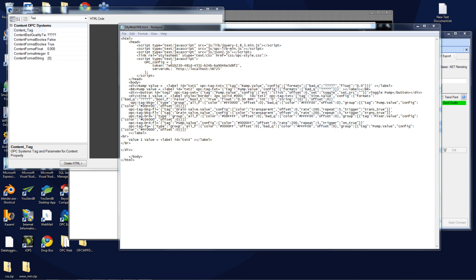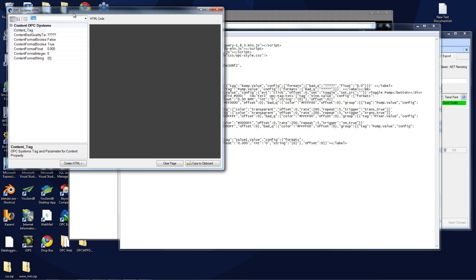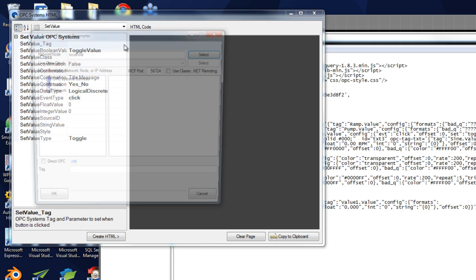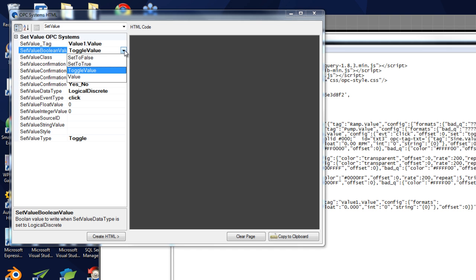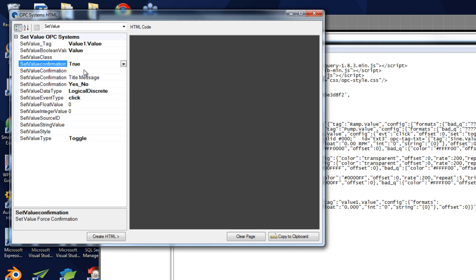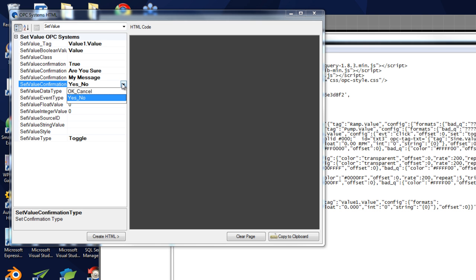One other important property to look at is the set value. This allows you to use any element in your HTML application to set a value in an OPC Systems tag. Currently you need to be monitoring that value for the set value to work. I've created a label called value1, given it an ID, and now we're going to monitor value1 through that particular tag. I'll paste the code to monitor that OPC Systems value1 tag, then select the set value property, pick the value1 tag — this is a floating point value. We can have a confirmation, so we'll set that to true, with a question of are you sure and a title message.